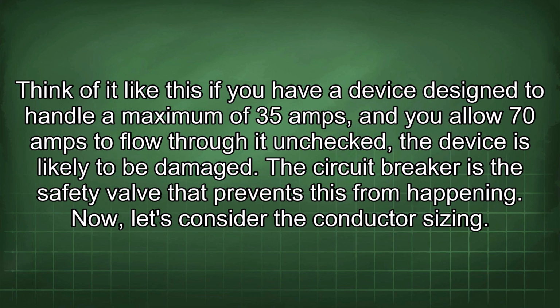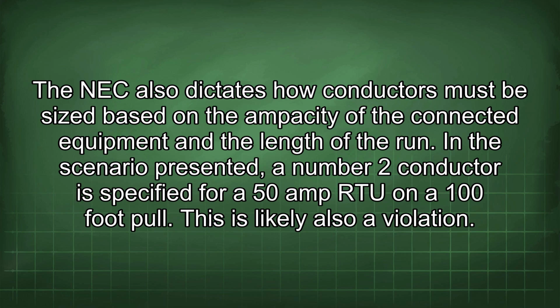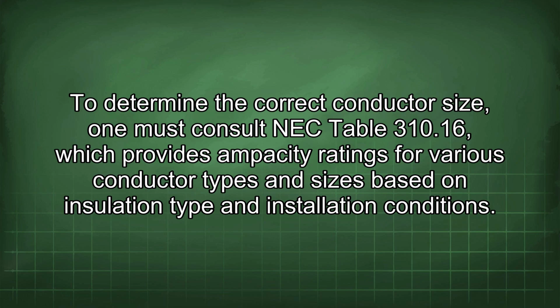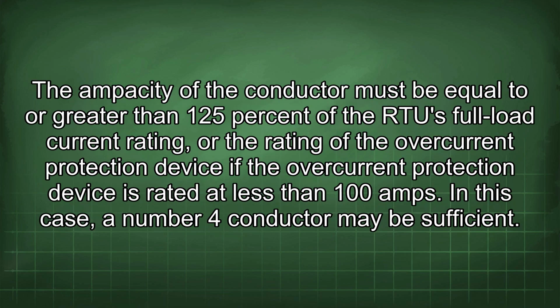Now let's consider the conductor sizing. The NEC also dictates how conductors must be sized based on the ampacity of the connected equipment and the length of the run. In the scenario presented, a number 2 conductor is specified for a 50 amp RTU on a 100-foot pull. This is likely also a violation. To determine the correct conductor size, one must consult NEC Table 310.16, which provides ampacity ratings for various conductor types and sizes based on insulation type and installation conditions. The ampacity of the conductor must be equal to or greater than 125% of the RTU full load current rating, or the rating of the overcurrent protection device if the overcurrent protection device is rated at less than 100 amps. In this case, a number 4 conductor may be sufficient.